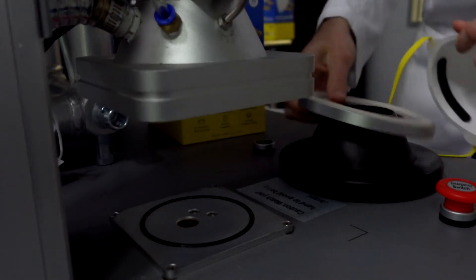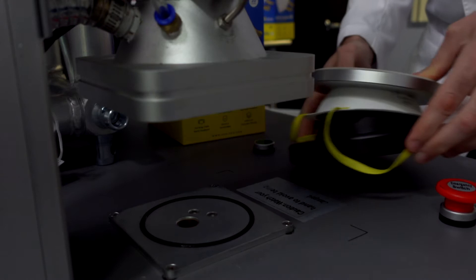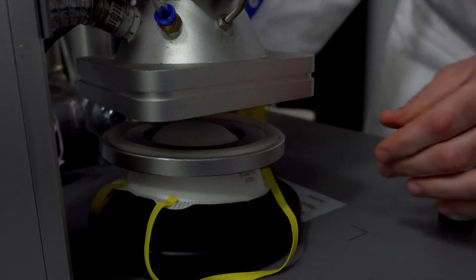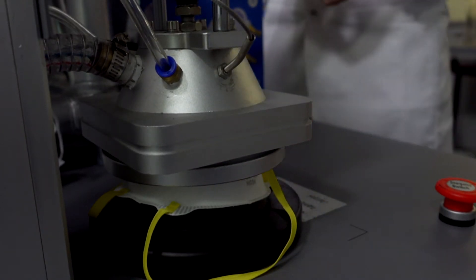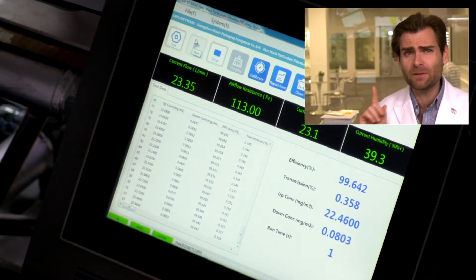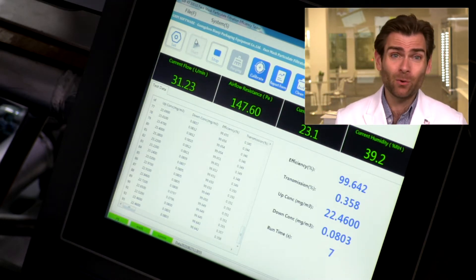If you're looking at our surgical mask videos, you're going to notice this is a little bit different. The setup is set to the NIOSH standard — we're using NaCl here. I'll put a link up top if you want to nerd out about how NIOSH does a different test than the FDA. And I'll let her rip — there's a PFE machine, a particulate filtration efficiency machine. Check out that link if you want to know more.